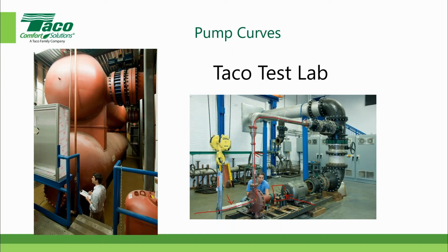So what happens is that the water flows into the pump this way, comes out vertically, continues down this pipe over here, and then this manual valve is a control valve. It's actually a manual control valve. That's important. We'll see why in a minute. The water continues across this pipe, goes through the wall, enters these buffer tanks, and each one of these is 10,000 gallons, comes out the top, and eventually, once all the piping's connected, goes right here, and then there's a flow meter. I'll just put FM here, that measures the flow in gallons per minute. And you can see the arrow here. And that's how we measure all of those 4 different components.